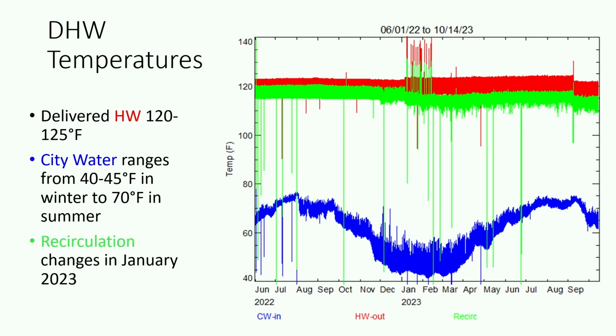So here's, not a surprise, city water temperatures. City main water temperatures vary a lot in the winter and the summer. It turns out when you have a city water main, it's closer to the air temperature than it is to the deep earth temperature, because the pipes are mostly at the surface, and it ranged from 40 or 45 in the winter up to 70 in the summer. And the interesting thing is, here's the hot water supply temperature, and here's the recirculation temperature. And at one point we did make some changes, and I'm going to talk about that.